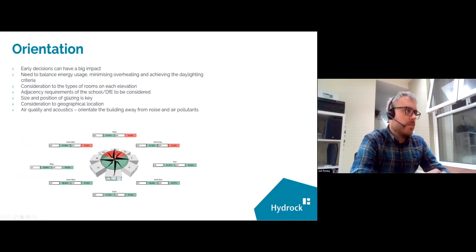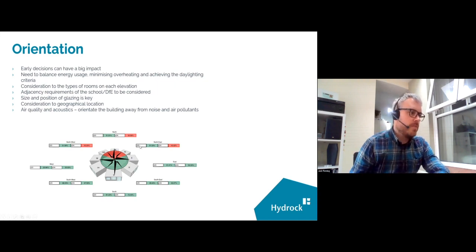When designing a school, early decisions can have a massive impact. One key consideration we get involved with soon after concept stage is orientation. There are certain orientations that make it much more difficult to pass daylighting requirements — the UDI and SDA metrics. Using a given window configuration, some orientations simply won't achieve compliance. Up to 20% of rooms are permitted to fail daylighting, but if you have many classrooms facing North, you'll struggle considerably.